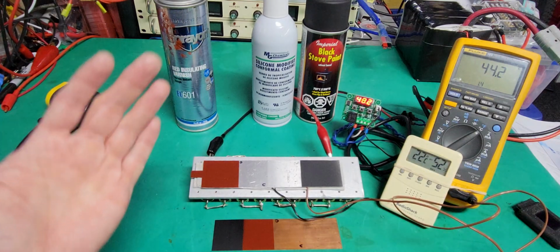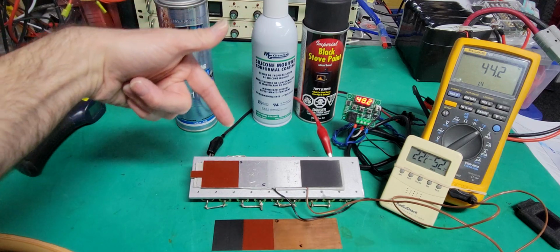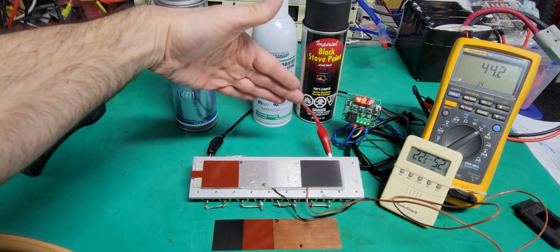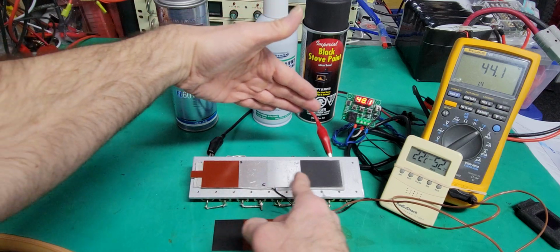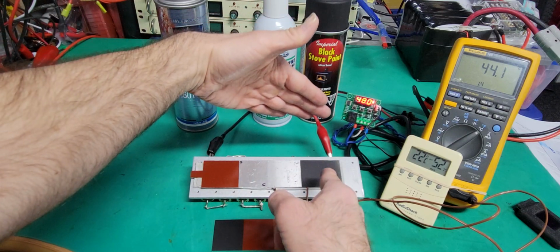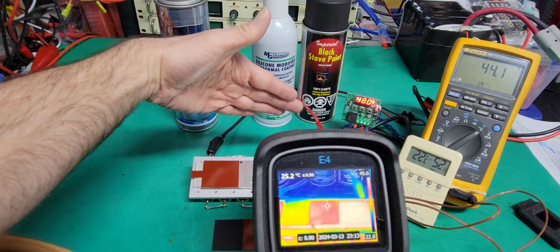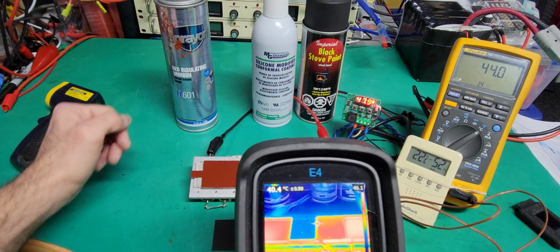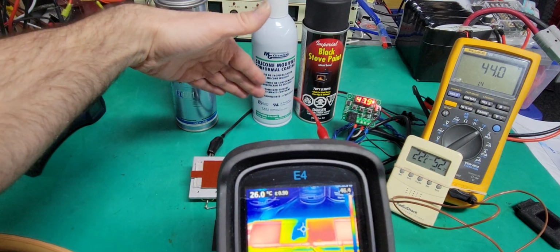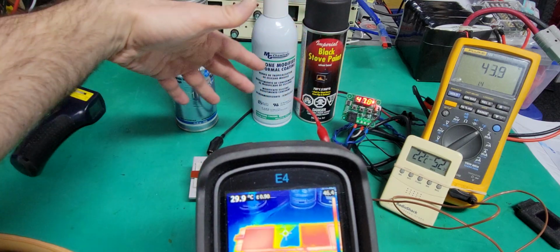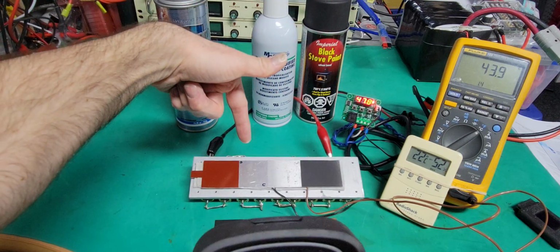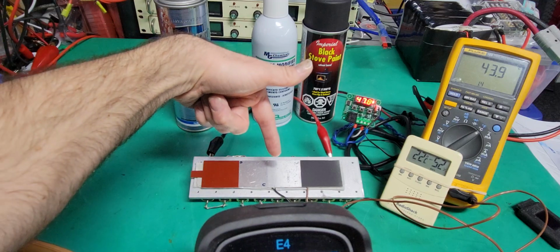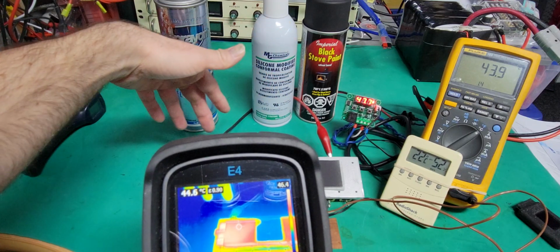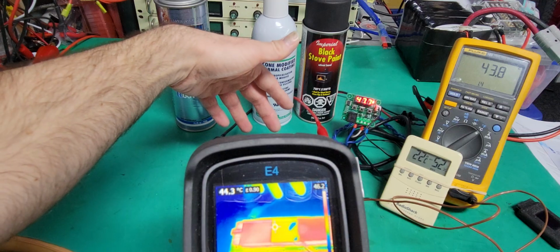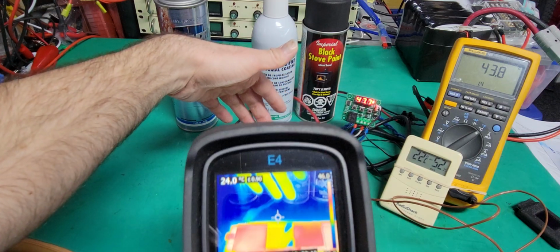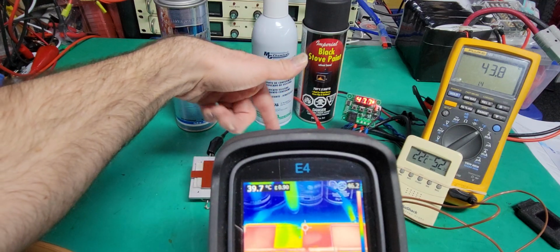And another thing very, very important is the reflection. So when I do this, you see the reflection of my hand a little bit, the visual reflection, okay? But you don't see it on the black. That is exactly the same happening with the thermal camera. What I will show you here is that you will see my hand reflecting in this surface here, you see? So you see it on this surface, on this one, and on this one. Just take a look. So you see a little bit, yeah? It's even worse than this one, and I mean worse, you see it more, and also on this one.